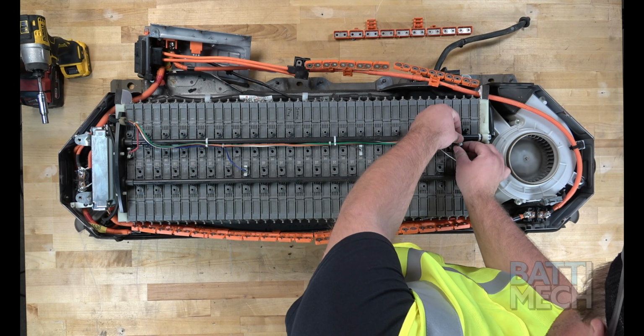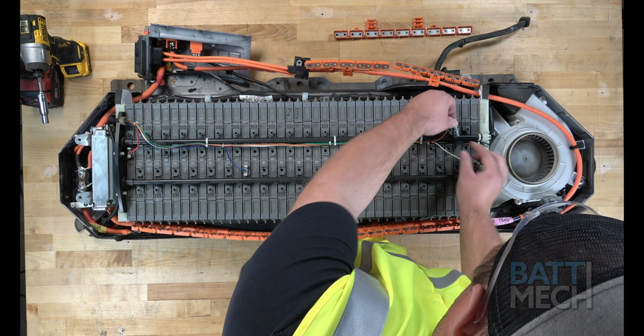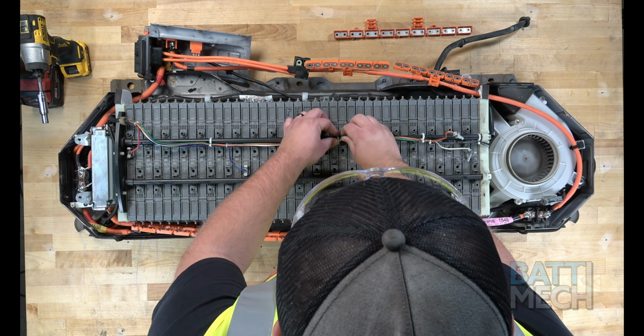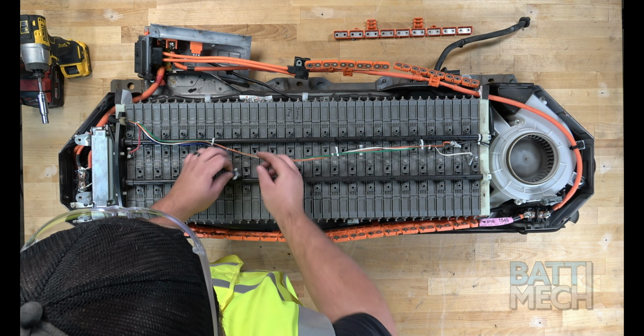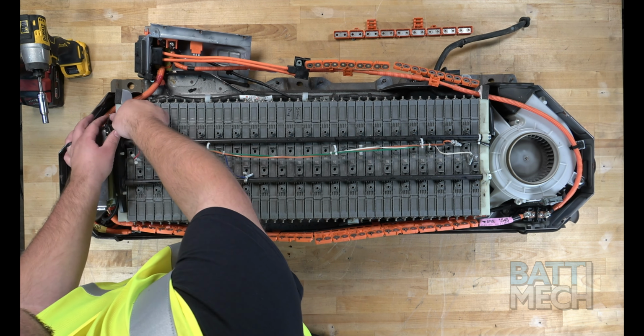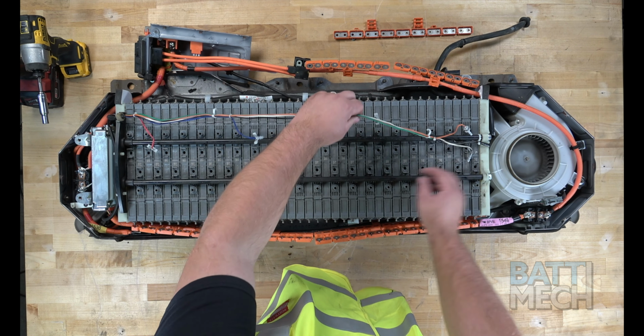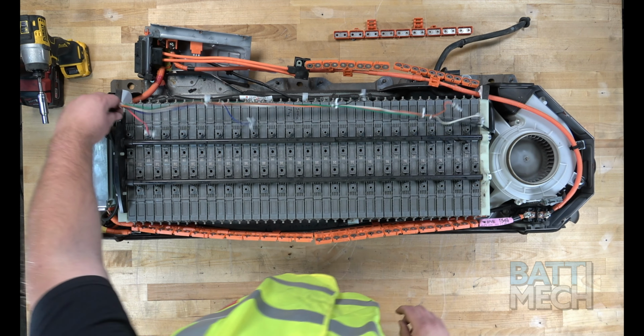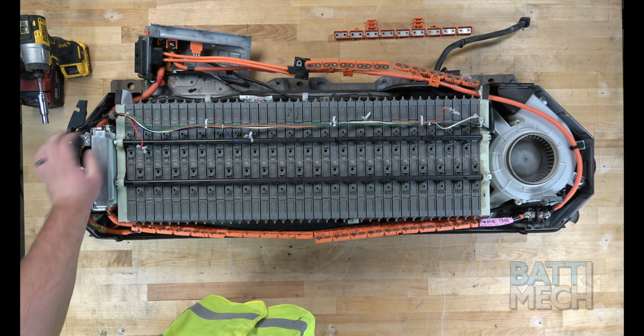Once the vent tubes are removed, we will go ahead and remove the temperature sensor from the top of the battery modules. Note, make sure to gently pull the wires away from the top, so when you flip the battery over later, the wires do not get damaged. Remove the black insert as well at this time.